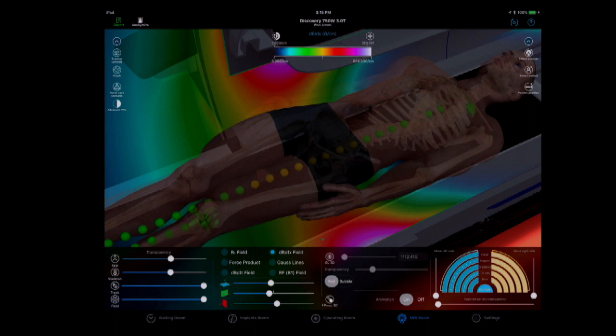Green, green, green, yellow, yellow, yellow, green, green, green. Can you see that? Seriously, guys, you all right with that? Do you see what I'm referring to? It's green, it's yellow, and then it goes back to green. And the pacer is green. So what's going on? For this energy, which is now being explained as dBdx, the maximum dBdx that this thing could tolerate was approached where it turned yellow.